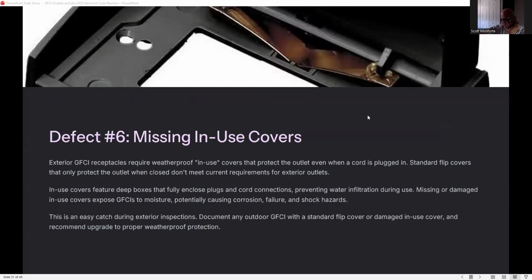Defect 6, missing in-use covers. Exterior GFCI receptacles require weatherproof in-use covers that protect the outlet even when a cord is plugged in. Standard flip covers that only protect the outlet when closed don't meet current requirements for exterior outlets. In-use covers feature deep boxes that fully enclose plugs and cord connections, preventing water infiltration during use. Missing or damaged in-use covers expose GFCIs to moisture, potentially causing corrosion failure or shock hazards. This is an easy catch during exterior inspections. Document any outdoor GFCI with standard flip covers or damaged in-use covers and recommend upgrade to proper waterproof protection. I personally hate these in-use covers because they're very difficult to open, and I've broken one or two of them just in frustration, but it is required.